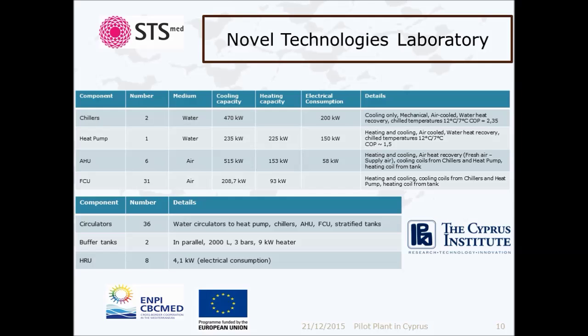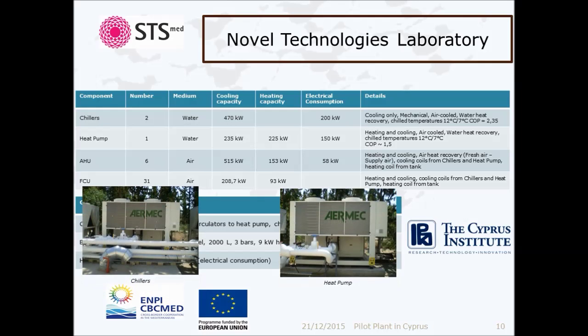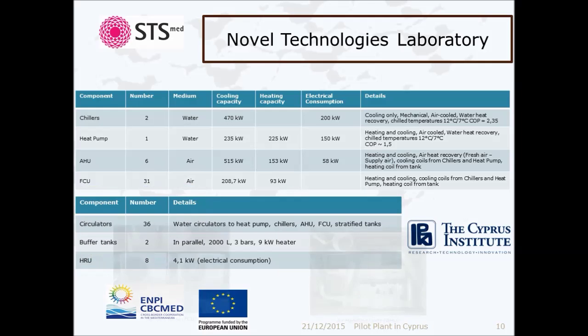The HVAC system of the Novel Technologies Laboratory was implemented before the installation of the Fresnel. Indeed, the NTL is in use since 2013, and the Fresnel collector was installed in 2015. So the solar cooling system is integrated to reduce the use of power elements such as 2 mechanical chillers and 1 heat pump. All these components provide cooling to the building, consuming huge amounts of electricity. Cooling and heating is then sent to the rooms with the help of numerous air handling units and fan coil units.